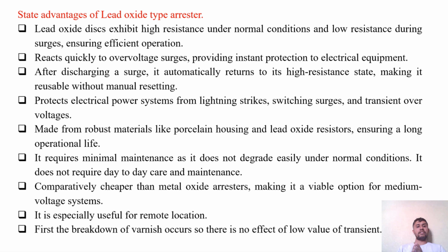It protects electrical power systems from lightning strikes, switching surges, and transient overvoltages. It is made from robust materials like porcelain housing and lead oxide resistors, ensuring a long operational life. It requires minimal maintenance as it does not degrade easily under normal conditions. It does not require day-to-day care and maintenance. It is comparatively cheaper than other metal oxide arresters, making it a viable option for medium voltage systems. It is especially useful for remote locations. First, the breakdown of varnish occurs, so there is no effect of low value of transient on the operation. So these are several advantages of lead oxide type arrestor.